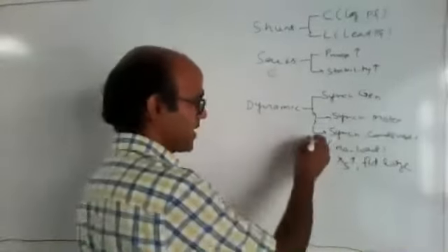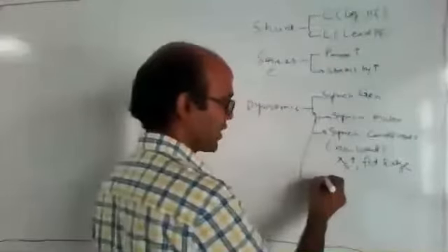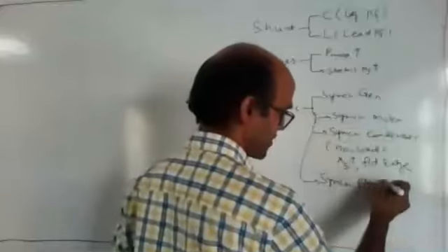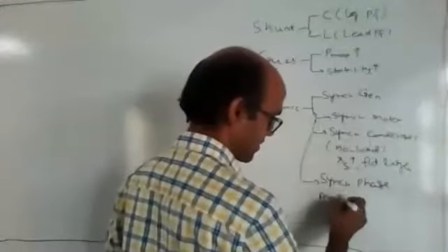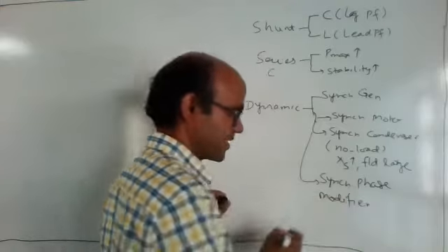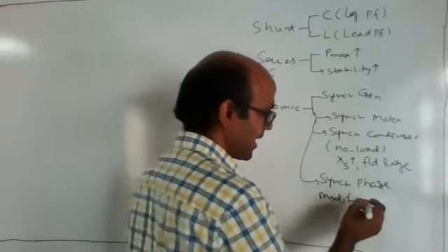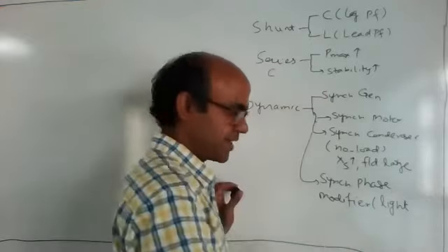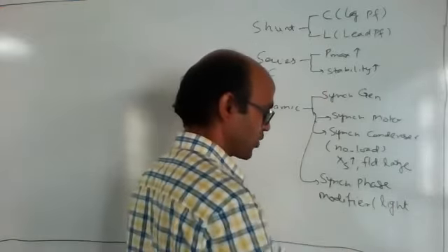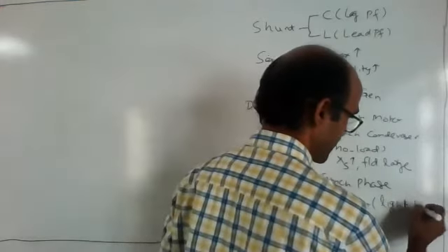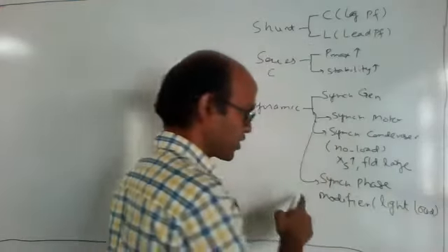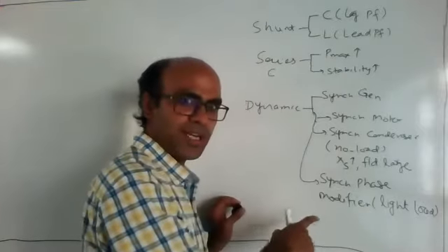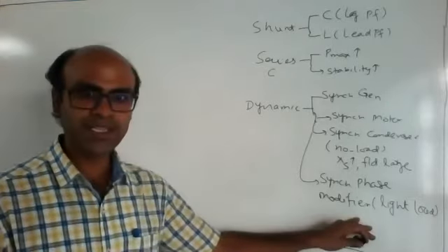And another one is the synchronous phase modifier. I have not discussed this, but it is used at light load. If we want to improve power factor at light load with a synchronous motor, then that motor is called a synchronous phase modifier. So this is a motor which is operating at light load conditions.